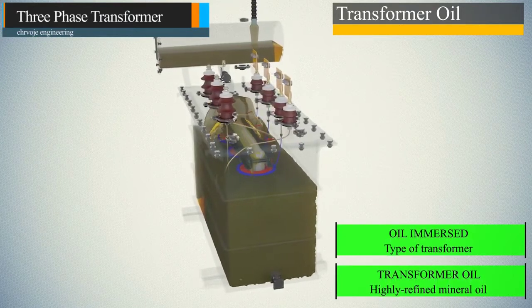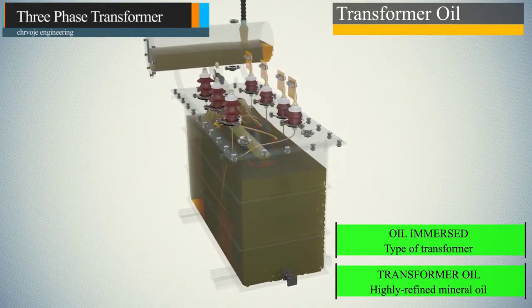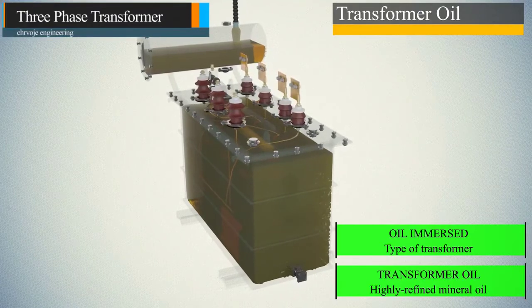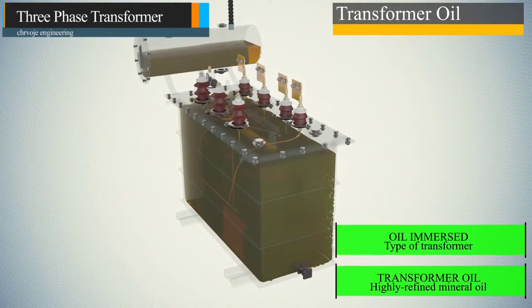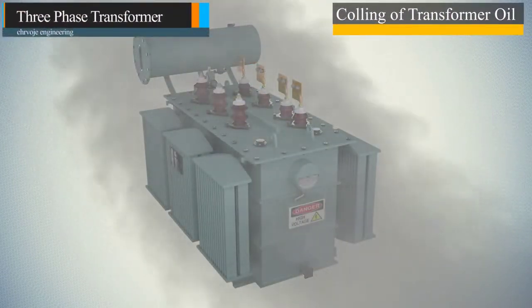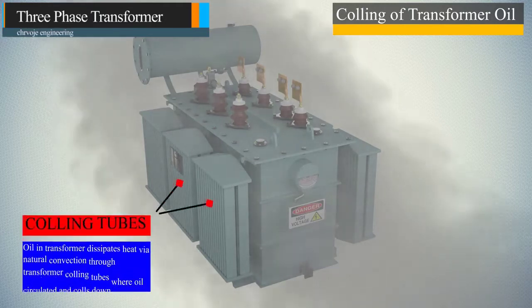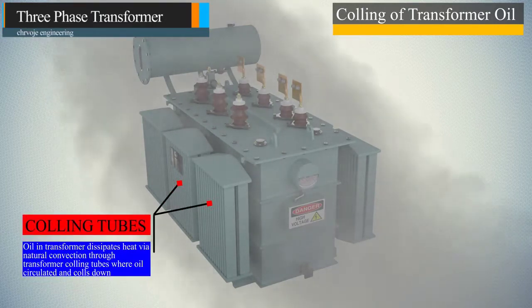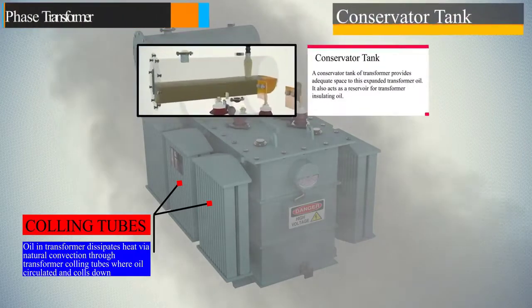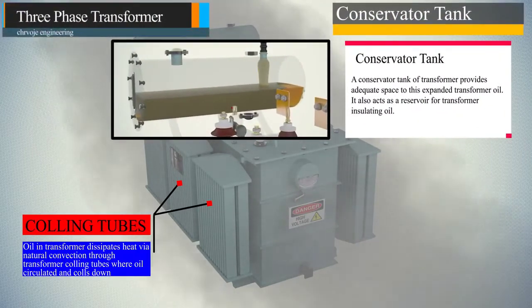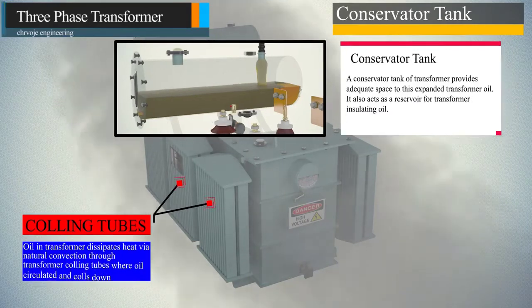Oil must therefore have high dielectric strength, thermal conductivity, and chemical stability, and must keep these properties on high temperatures for extended periods. The oil in the transformer dissipates heat via natural convection through transformer cooling tubes, where oil circulates and cools down. When ambient temperature rises, the volume of oil inside the transformer increases. A conservator tank of transformer provides adequate space to this expanded transformer oil. It also acts as a reservoir for transformer insulating oil.